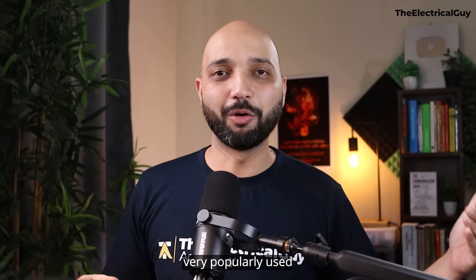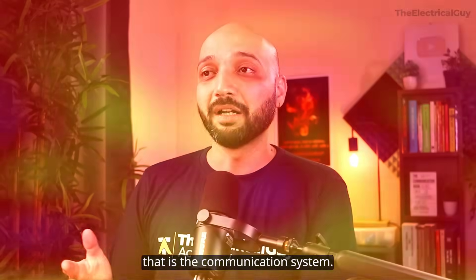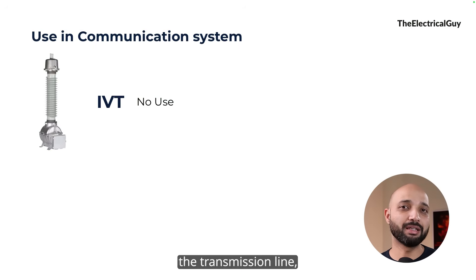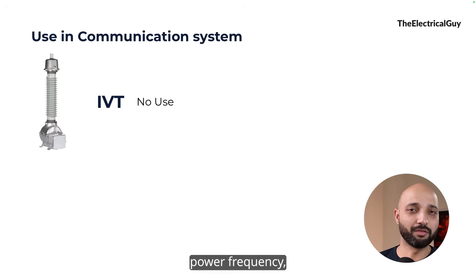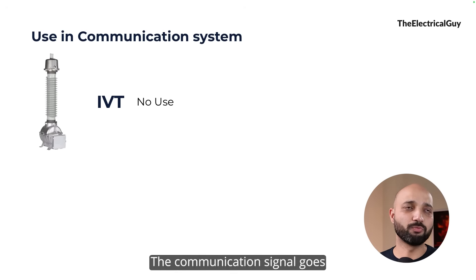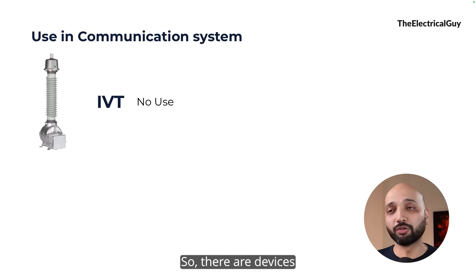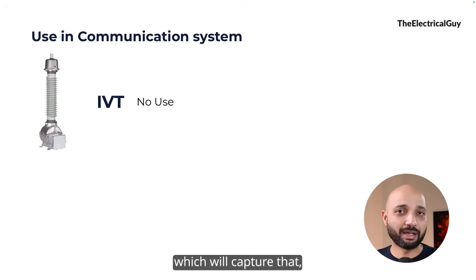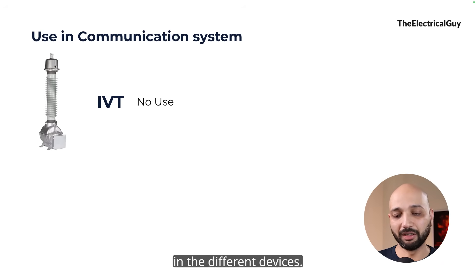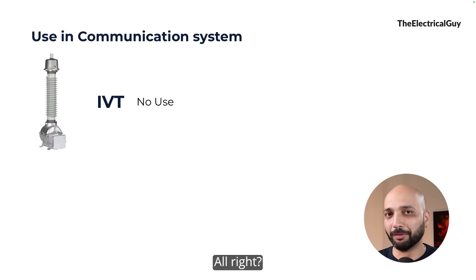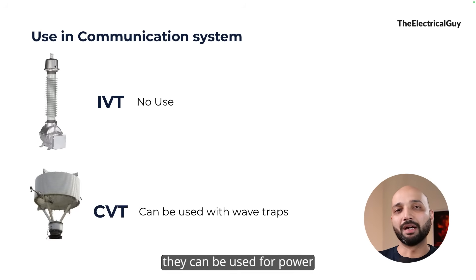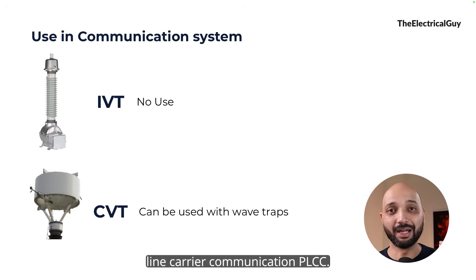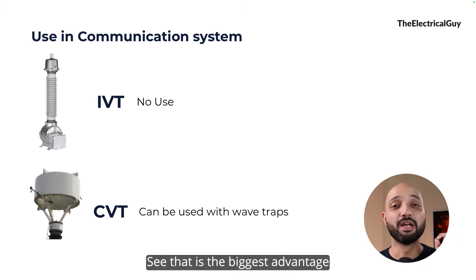The last and most important point — and the reason CVTs are very popularly used in high voltage applications — is their role in communication systems. Transmission lines not only transmit power but can also carry communication signals at very high frequencies, around 500 kHz, compared to the power frequency of 50 to 60 Hz. IVTs play no role in this function, but CVTs, when coupled with wave traps, can be used for power line carrier communication — PLCC. This is the biggest advantage CVTs offer.